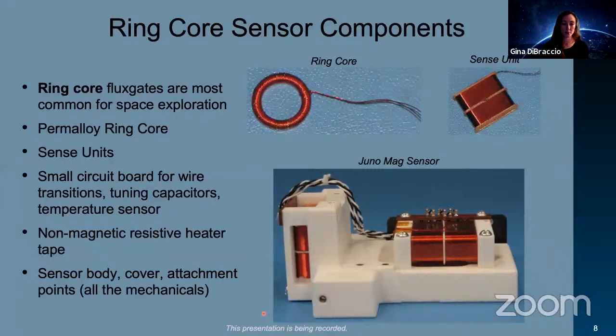The ring core components consist of a permalloy ring core, which you can see in the center here. We have a picture of one of our ring cores that we use. We have sense units over here on the right, which essentially look like a solenoid. The other components include a small circuit board used for wire transitions, tuning capacitors, temperature sensors, non-magnetic resistive heater tape, and other components to assemble the entire structure, such as the sensor body, the cover, and the attachment points.